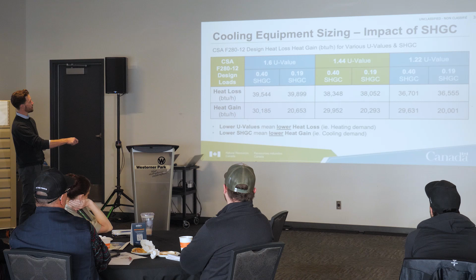So let's talk a little bit, as this house as a system thinking, about the interplay between the solar heat gain of the windows you choose and the mechanical systems you're putting in this house. So what we have here is the same chart, same 3 window U-values across the top, same 2 choices for solar heat gain for each one. Below that you have the heat loss in BTU per hour and the heat gain in BTU per hour for the house across the board. Now, something you'll notice here is that for any given window, between the 2 solar heat gain choices, the heat loss number hardly moves at all.